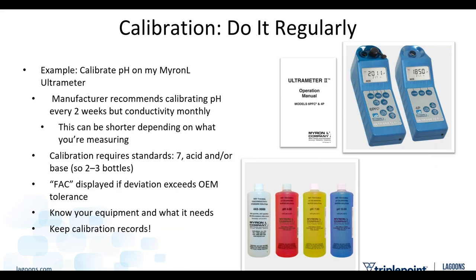So I've had, I don't know, probably a half dozen or so Myron L Ultrameter 6s over the years. It's my favorite meter for pH, conductivity, TDS, stuff like that. I can tell you that the manufacturer's recommendation was not in line with my employer's recommendation. The manufacturer said do pH every two weeks and conductivity monthly. My employer insisted on weekly calibrations. If I saw more than a 10% drift, I had to go to daily calibrations.